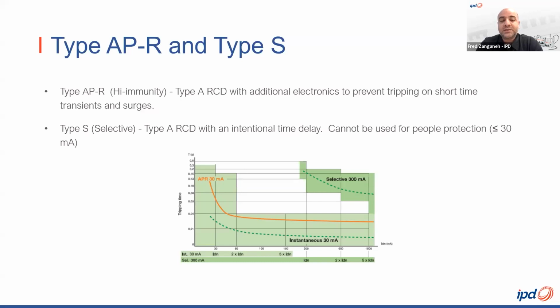The selective RCDs are rated 100 milliamp or 300 milliamp, and as they have a non-instantaneous operation, they cannot be used for final sub-circuit protection or 30 milliamp. The selective RCDs are sometimes used for additional protection against the risk of fire caused by a current leakage across insulation.